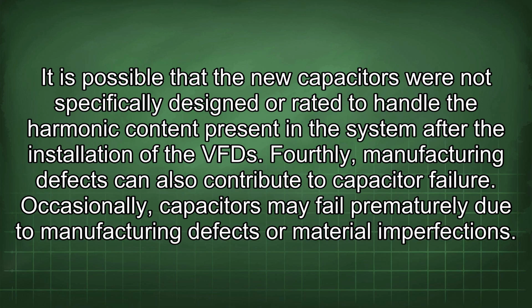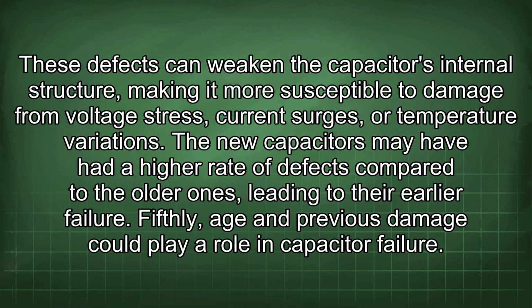Fourthly, manufacturing defects can also contribute to capacitor failure. Occasionally, capacitors may fail prematurely due to manufacturing defects or material imperfections. These defects can weaken the capacitor's internal structure, making it more susceptible to damage from voltage stress, current surges, or temperature variations. The new capacitors may have had a higher rate of defects compared to the older ones, leading to their earlier failure. Fifthly, age and previous damage could play a role in capacitor failure.